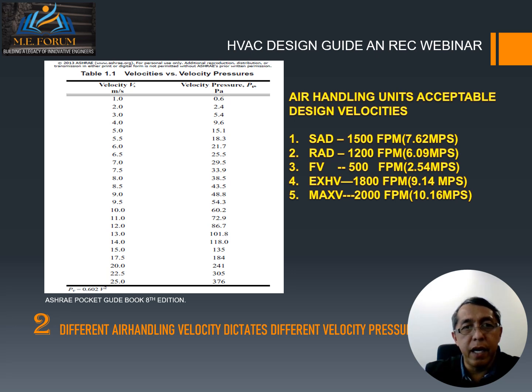So for supply air duct, I normally use 1,500 feet per minute. Return air duct, 1,200 feet per minute. Face velocity on diffuser or grills or louvers, 500 feet per minute. Exhaust velocity is 1,800 feet per minute. Maximum velocity normally used when doing value engineering is about 2,000 feet per minute.